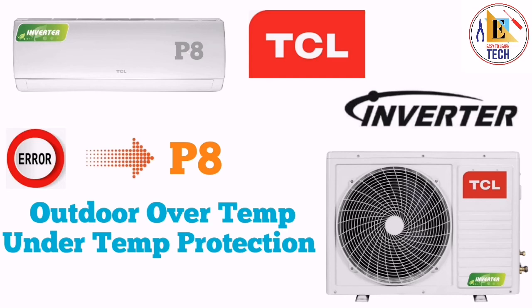And if your ambient temperature is between -1 and 33 degrees Celsius and it shows the error P8, then you have to check the temperature sensor resistance, and if it is 5 kilo ohms, it means your sensor is good. If there is any other problem, then you have to go to the indoor unit and check. If indoor is showing some error, then you have to sort out the error. Your unit will be in working condition.